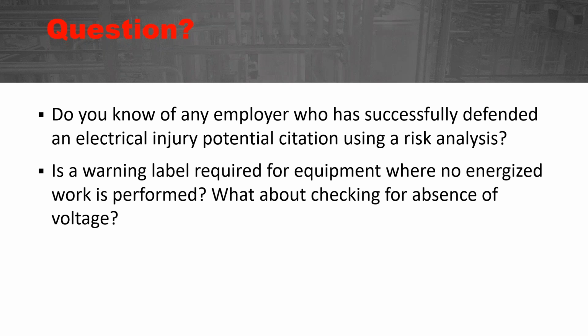You're testing on the outside of the equipment with test probes, and not only are the contacts safe, Grace went steps beyond that and made it safe that even if you were to stick in paper clips, you're not going to get shocked because of the built-in impedance. So you can do your testing from the outside without opening up the equipment. Now, until more and more places get these installed, the worker is going to have to open up the equipment, even if it's de-energized, to test for the absence of voltage and to go through our steps of establishing and verifying the equipment is in an electrically safe work condition. So I see a great need for equipment that really needs to be labeled at that point.